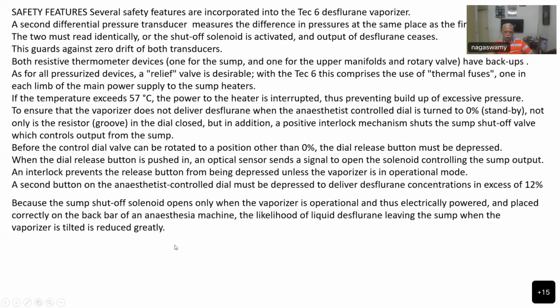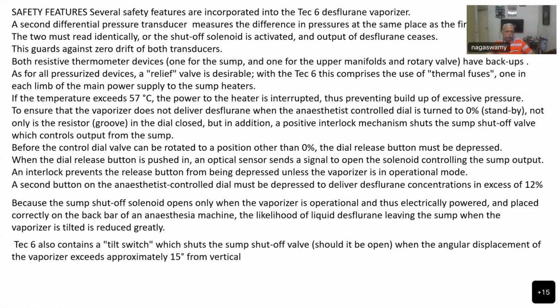So that is another important safety feature, and it also contains a tilt switch. In addition to that, there is a tilt switch which shuts the sump shut-off valve. That solenoid valve, which shuts off the sump, is open, and when the angular displacement of the vaporizer exceeds approximately 15 degrees from vertical, again that solenoid valve will close. So that solenoid valve is a very important part of this machine to prevent any vapor spilling out from the sump into the tubing that is going to get mixed with the fresh gas flow.